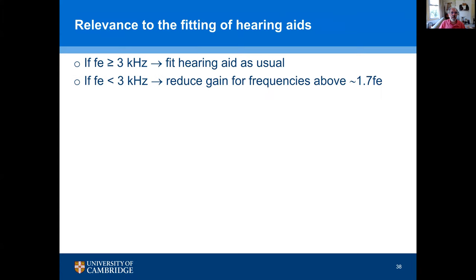How do we apply this to the fitting of hearing aids? We've developed a rule of thumb: if the edge frequency is greater than 3 kHz, fit the hearing aid as usual without changing your normal fitting method. But if the edge frequency is below 3 kHz, we recommend reducing the gain for frequencies above 1.7 times the edge frequency. A number of studies have found that this gives better results than standard fitting methods.